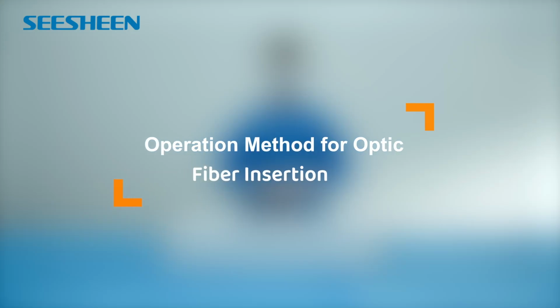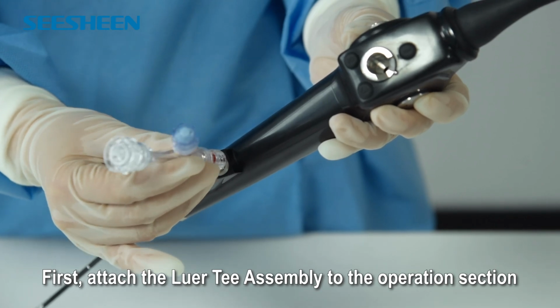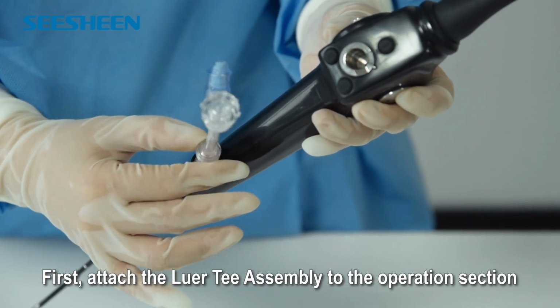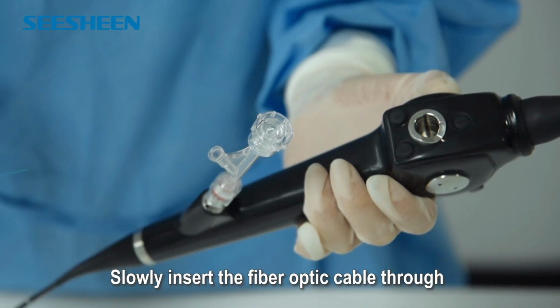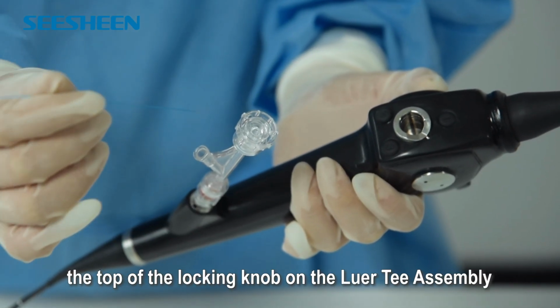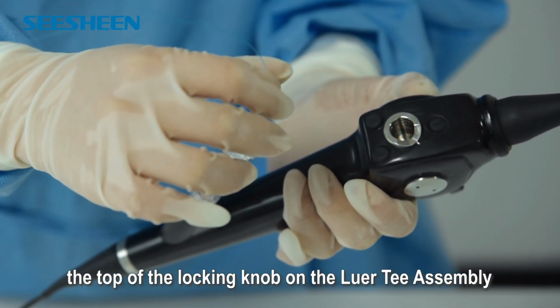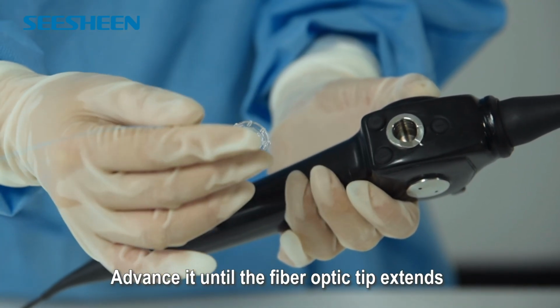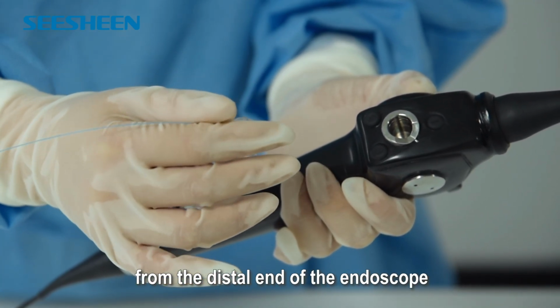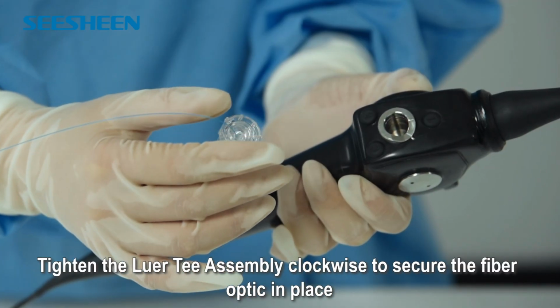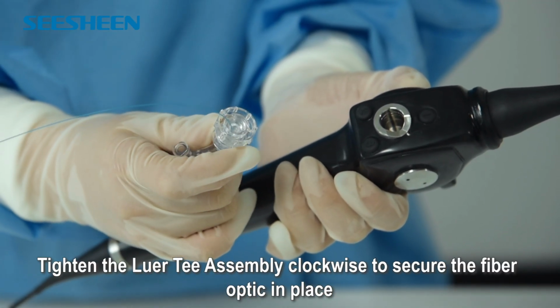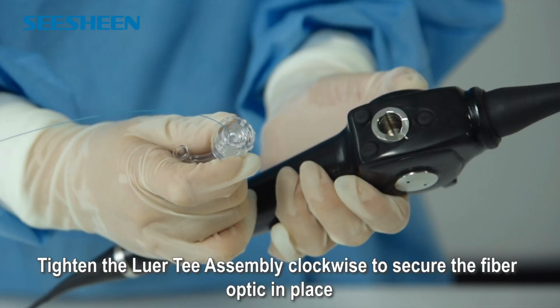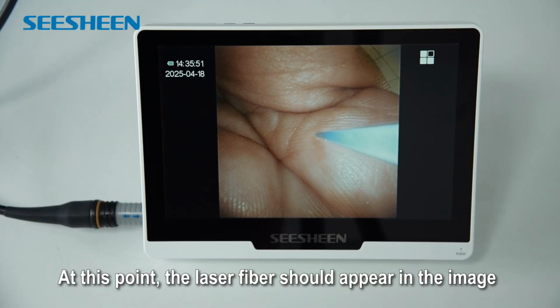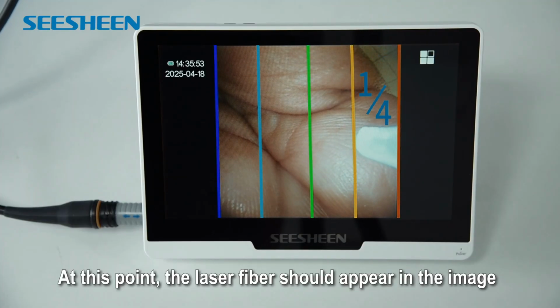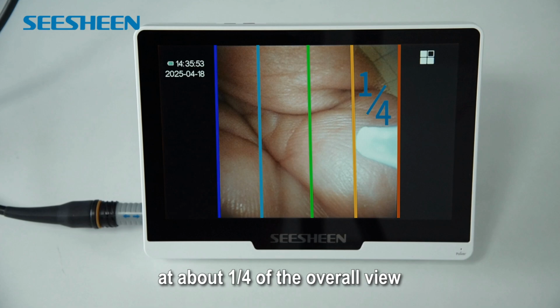Operation method for optic fiber insertion. First, attach the Luer Tee Assembly to the operation section. Slowly insert the fiber optic cable through the top of the locking knob on the Luer Tee Assembly. Advance it until the fiber optic tip extends from the distal end of the endoscope. Tighten the Luer Tee Assembly clockwise to secure the fiber optic in place. At this point, the laser fiber should appear in the image, at about 1/4 of the overall view.